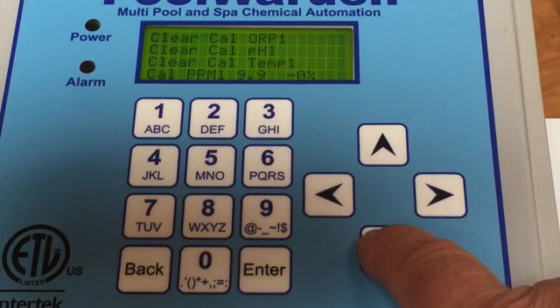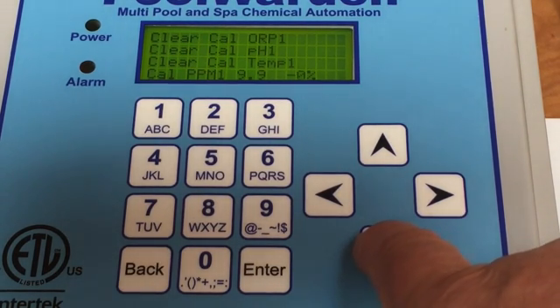Then go down here and you can calibrate your parts per million sensor. Typically you'll want to leave that alone, even if the ppm isn't exactly matching up to your test kit, because this will take a DPD reading either every 10, 20, 30, or 60 minutes. So this isn't always real time.